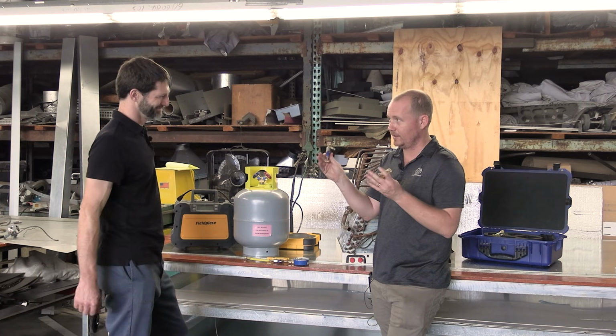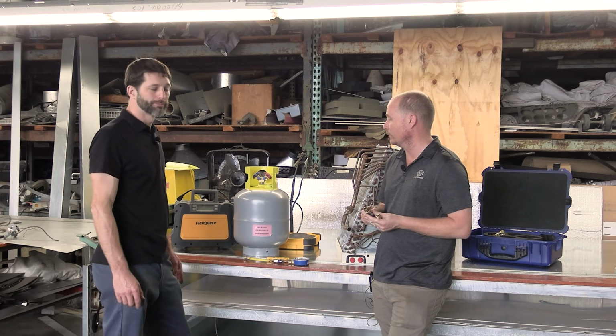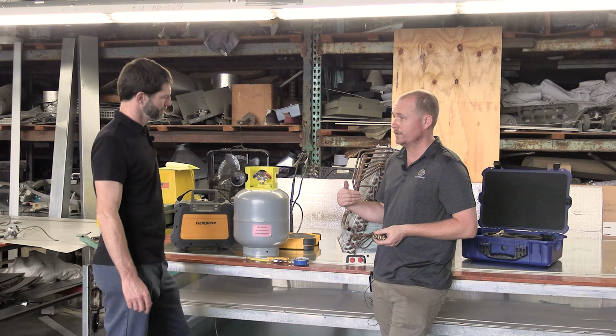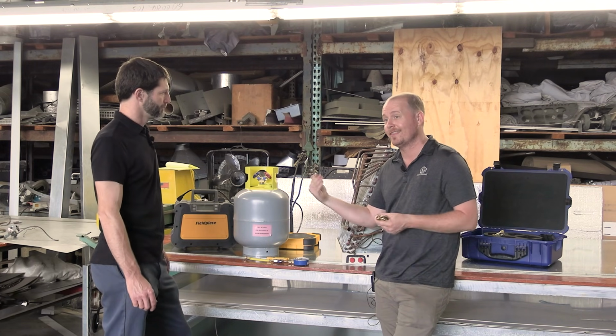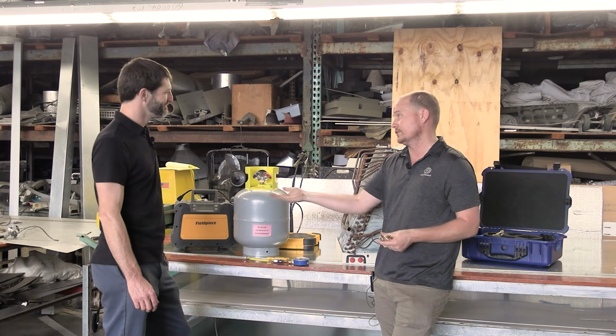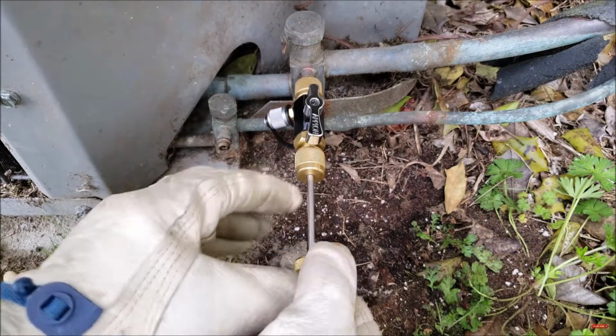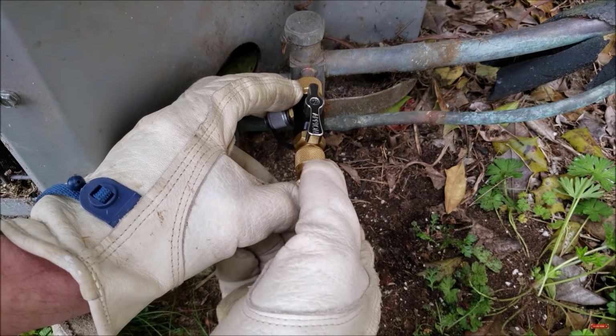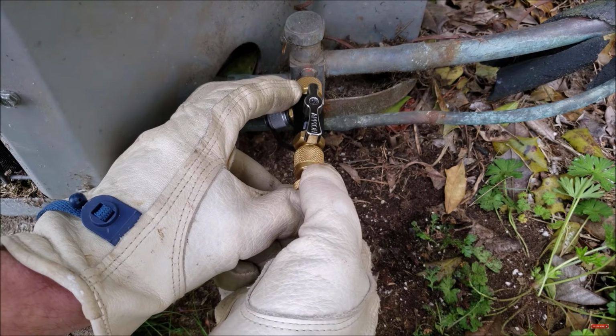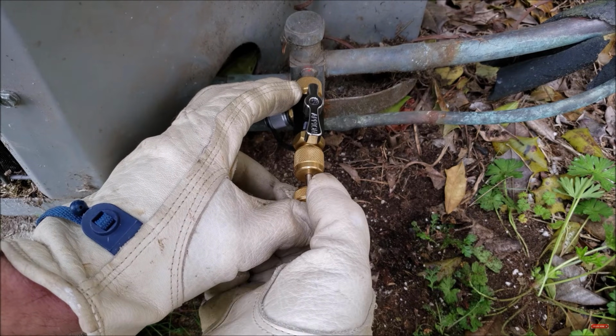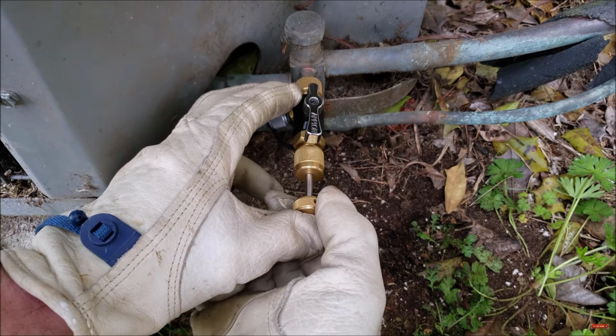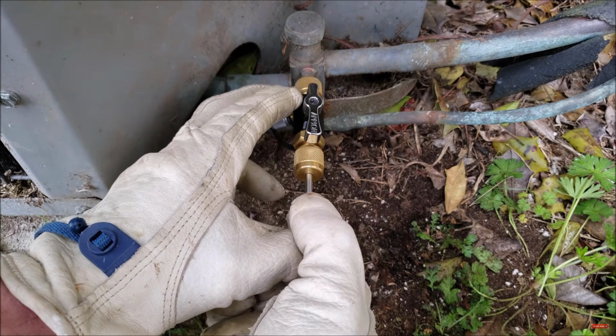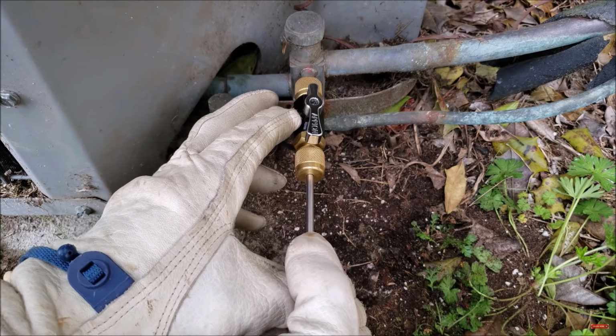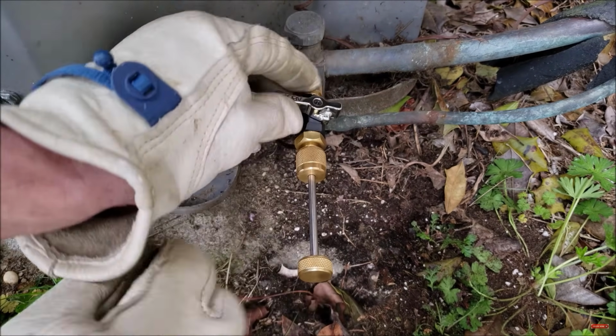Yeah, and that's why having a couple core tools is really, really important when you're going to recover refrigerant, because it's just going to make it so much quicker. And then when you have your cores out, that's also going to make it easier to pull your vacuum afterwards. So get your cores out, leave these core tools in place when you're recovering. The mistake I see happen a lot is they think that they've got to pull the core out and then get the core tools off. Leave them on through that whole process, and then you're just going to connect to this back side.